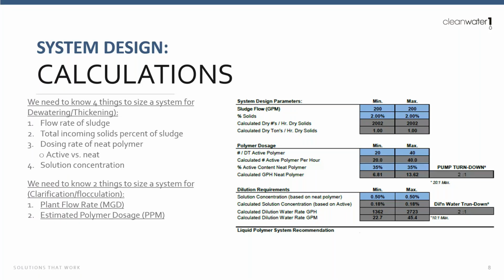In reference to dewatering and thickening, we're looking at the flow rate of the sludge going to the dewatering or thickening device. And of that sludge, we're looking at total percent solids incoming. Then we need to understand the dosage rate of the polymer, right? But the caveat there is we need to understand whether we're looking at that as an active or a neat basis. If you look over to the chart on your right, this is an emulsion polymer sizing sheet that we use for neat polymer. And you'll see that there's actually a line in there to input your active polymer content.